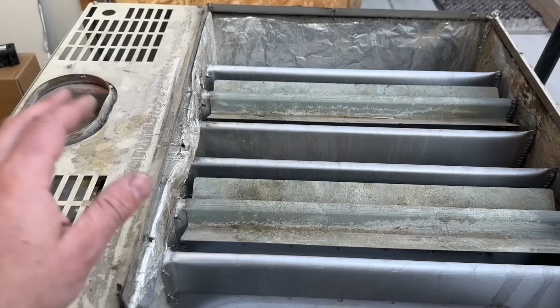All right, so as we said before, this is all you need. You can actually use a long lighter if you want, but these matches are really long, so you can really get it deep down into the heat exchanger. So we're going to light one of these matches and show you how to do this test. Now, to be extra safe, you could just go ahead and shut the gas valve off, even though this is what's allowing gas to flow through. So if your furnace is not calling for heat, you have this door switch open, you're totally safe. But if you want to, you can close that gas valve off just to make sure that you're extra safe.